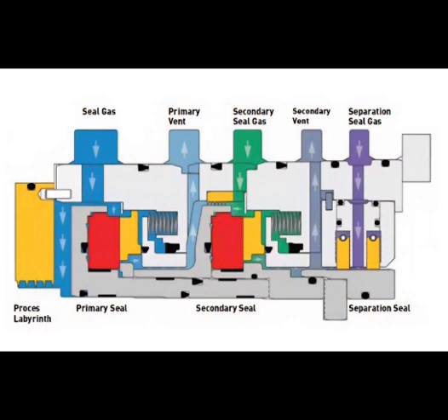This gas is injected between the 2 separation seal elements, providing a barrier between the atmospheric bearing housing and the dry gas seal. If a labyrinth, it is injected between the 2 sections of teeth. If a carbon ring type seal, then between a pair of carbon rings. Typically, separation seal gas is an inert gas, like nitrogen, but air may also be used. If using air, particular care must be taken to avoid creating explosive mixtures in the secondary vent. These can be pressure or flow controlled dependent on customer preference.